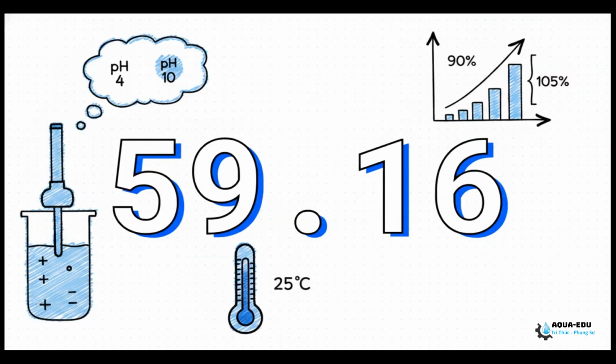So I really want you to burn this specific number into your memory. 59.16. When you go to check the calibration in your pH 4 or pH 10 buffers, remember that our ideal acid slope is 59.16 millivolts per pH unit, assuming we're at 25 degrees Celsius. We absolutely need to see that slope sitting healthy between 90 and 105%. If it drops outside that range, the sensor just isn't responding correctly to the hydrogen ions in the water anymore.